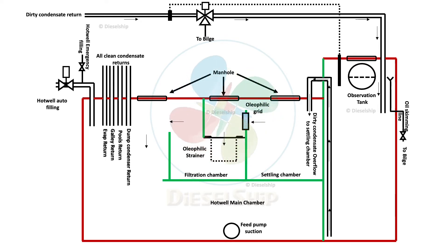How do we remove oil? If there is any contamination, the only way we can remove it is through the skimming line. It is a funneled mouth pointing upwards because the oil always stays on top. The top layer can be skimmed using the skimming valve. To skim, we open this valve, which will start draining the content from the top. It removes the oil, not the water.